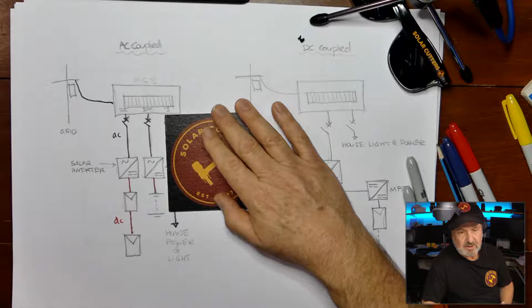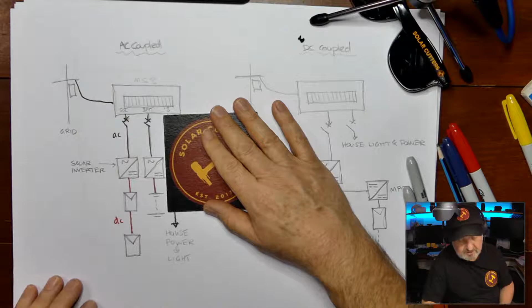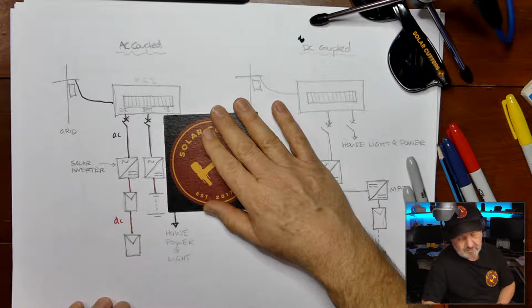That is an implication which needs to be considered when you get an approval to connect. So when you are adding an inverter onto the utility grid, they will want to go through an approval process. Different states have different rules around this, how it works, and different DNSPs. But effectively, this is limited. You just can't keep adding inverters and saying, don't worry about it, we're not going to export any, because they do have an impact on the grid itself.